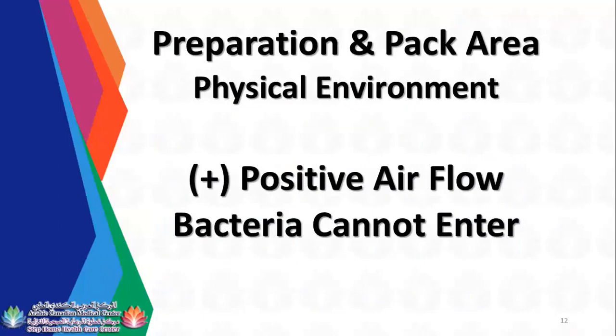So for the preparation and pack area physical environment, it should have positive airflow. With positive airflow, bacteria cannot enter that room or area. Please remember that your decontamination area should have negative airflow, or negative air pressure, which means the bacteria cannot escape the room, while the prep and pack and other areas of the CSSD have positive airflow, so bacteria cannot enter those rooms.